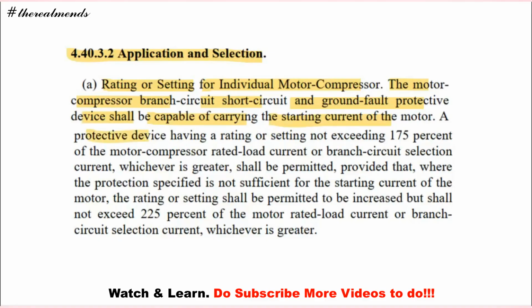So a protective device having a rating or setting not exceeding 175% of the motor compressor's rated load current. So our branch circuit selection current, whichever is greater shall be permitted. So provided that where protection specified is not sufficient for the starting current of the motor, the rating shall be permitted to increase but shall not exceed 225% of the motor rated load current.